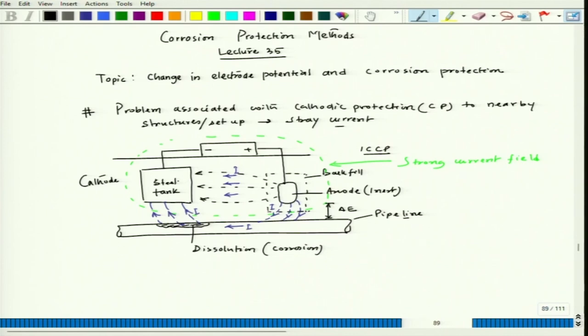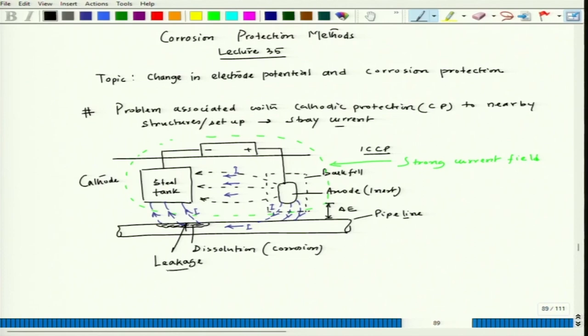The cathode — the steel tank — is still protected, but this particular pipeline stationed close to it does not have any cathodic protection. The part from which current leaves, due to current flow within the pipeline caused by the potential difference near the strong current field, will corrode, and there could be a possibility of leakage. The current flowing into the nearby pipeline due to the potential difference is nothing but the stray current.